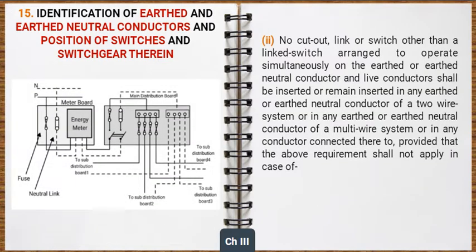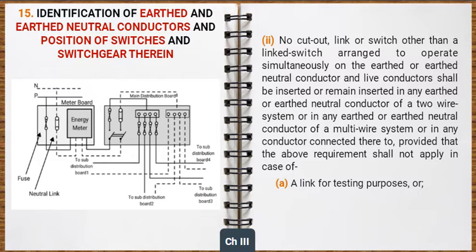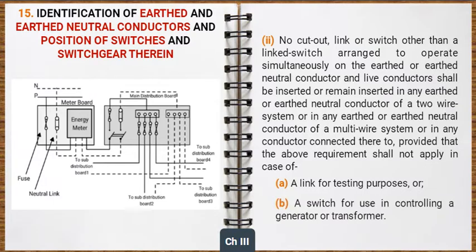No cut-out, link or switch other than a linked switch arranged to operate simultaneously on the earthed or earthed neutral conductor and live conductors shall be inserted or remain inserted in any earthed or earthed neutral conductor of a two-wire or multi-wire system, or in any conductor connected thereto. This requirement shall not apply in the case of a link for testing purposes or a switch for use in controlling a generator or transformer.